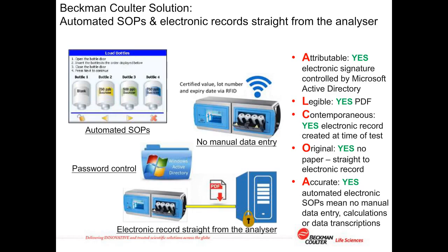No, actually, you can set it so it automatically exports the files on a daily basis at a fixed time. So it collates the data, it collates the electronic records in the analyzer, and then every day at a certain fixed time sends them out across the Ethernet network to the secure server on the site.